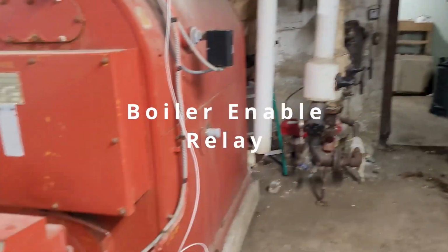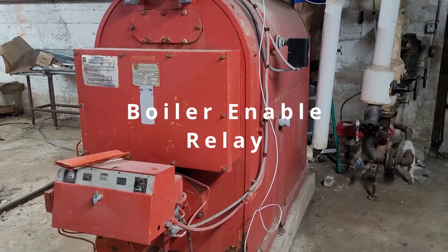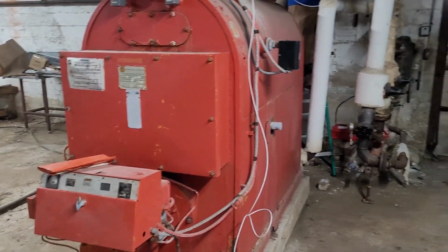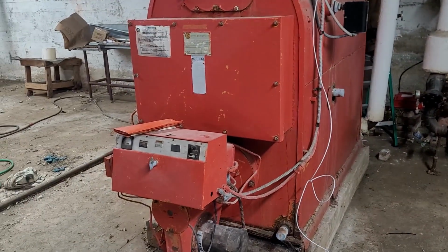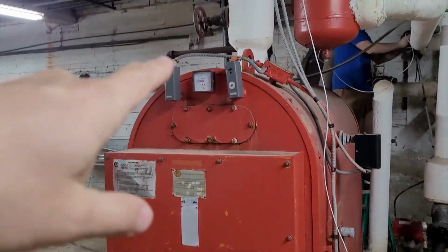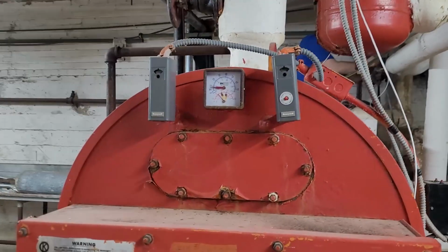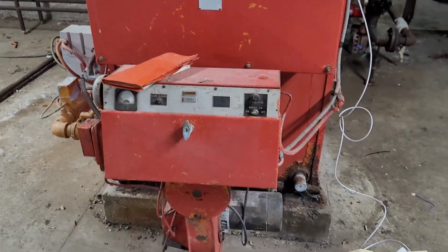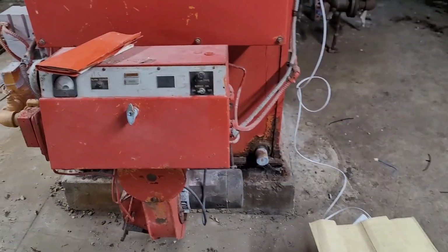Okay, so we're putting this plant controller on this boiler and boiler pump. All right, so this boiler's from 1976. The pump runs all the time, the boiler's enabled all the time, and then it just meets a set point. So you set the temperature on the dial and it just cycles as it should. Well, we want to put a relay on this boiler and get a start-stop.